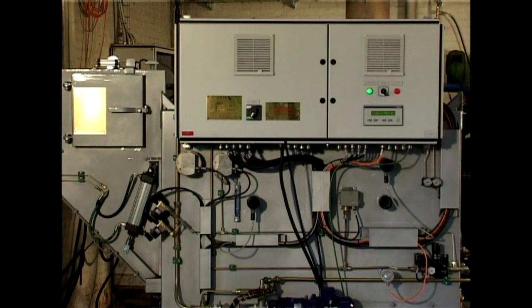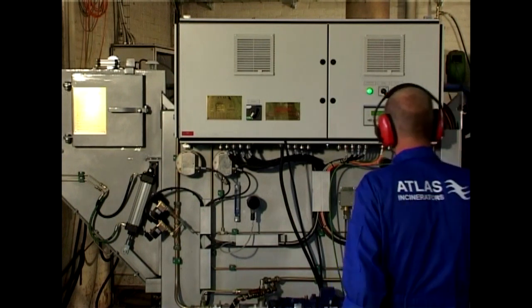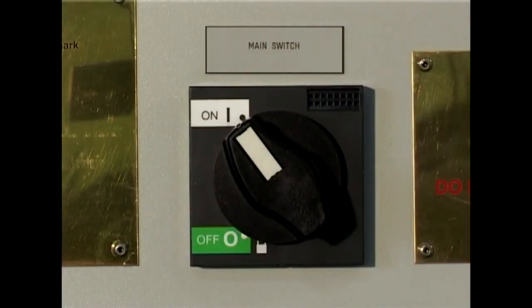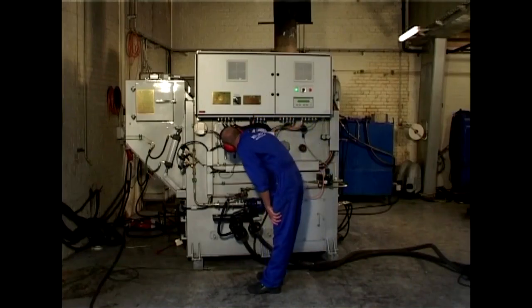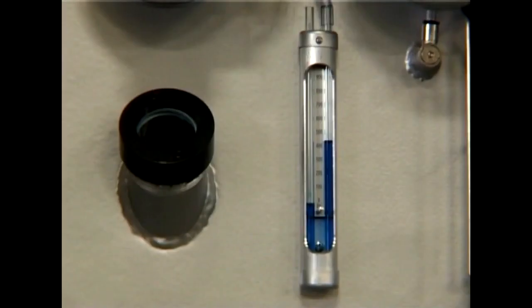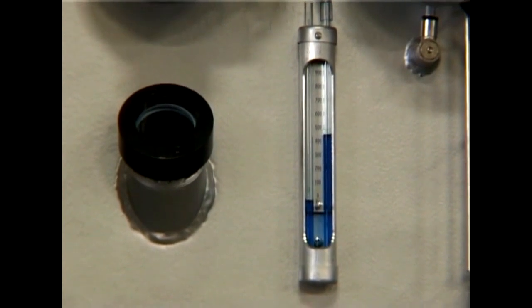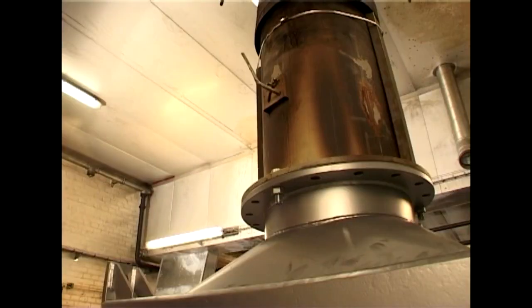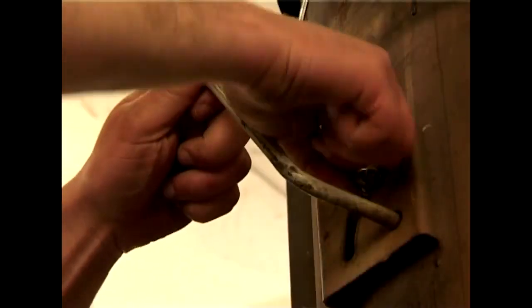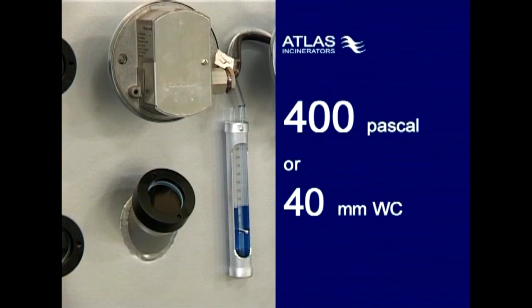Before using the incinerator, you will need to prepare it for operation. To do so, start by turning the incinerator main switch to the on position if it's not already done. You are now ready to go through the preparation process. To secure that no flue gases escape to the machinery room, you should always ensure that you have vacuum in the combustion chamber. The vacuum can be checked on the U-tube. On the flue gas outlet, close the damper until you have approximately 400 Pascal vacuum on the U-tube.